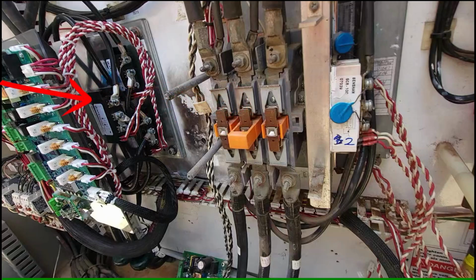contact closed. And so once this particular style of starter, once the SCRs have gotten to where they can stay fully closed, by fully closed, that means they're just acting as a pass-through device. They're no longer adjusting how much power is going through them. Once they've fully closed and the motor is technically at speed, then we will transition and we can close the starter here to have just the hard mechanical contact, and then we can open these up to allow these to come out of the load circuit.